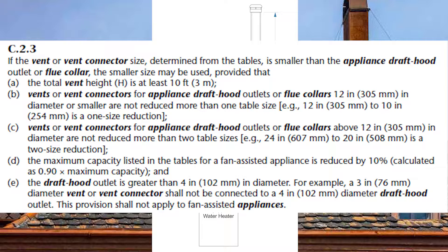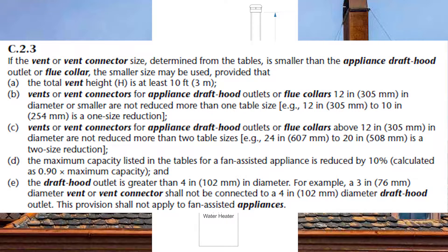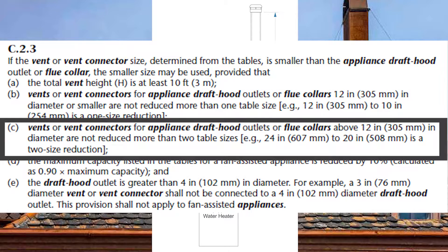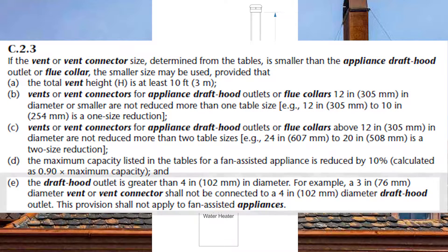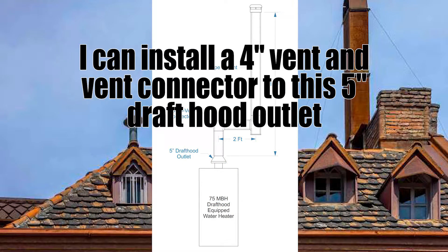There are a few requirements we need to follow to be able to do this. First, the vent height needs to be at least 10 feet tall. In our example the vent height is 15 feet, so we've met the first requirement. The next two requirements come down to sizing: if the draft hood outlet or flue collar is 12 inches or less, we may reduce by one table size; if it's greater than 12 inches, we can reduce by two table sizes. In my example I have a five-inch draft hood outlet, so I can only reduce by one table size. The last requirement, specifically for draft hood equipped appliances, is that the draft hood must be greater than four inches — which we are at five — so I can reduce by one table value, down to four inches.